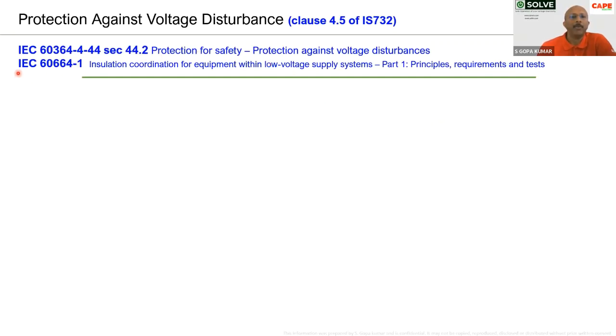In parallel, we also should look at the standard IEC 60664, insulation coordination of equipment within low voltage supply system, part 1, principles, requirements and tests. Basically, I am referring to a standard which is a little bit new. 60664 is not a new standard, but I am referring to the 2020 edition, which has added a lot of special requirements and testing measures for electrical or electronic equipment, which need to be made mandatory in India in order to have a safe installation.